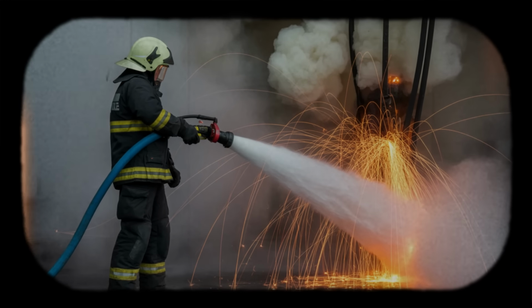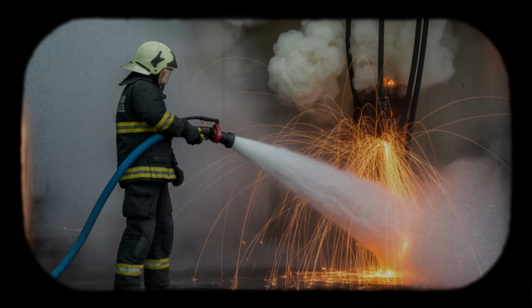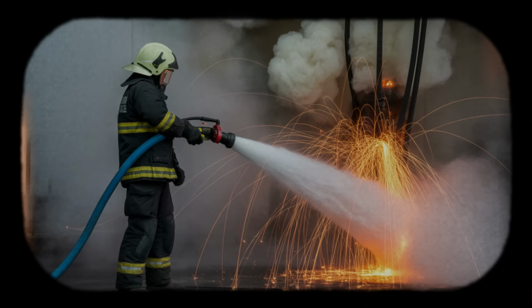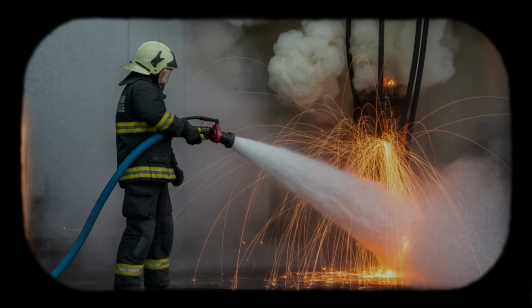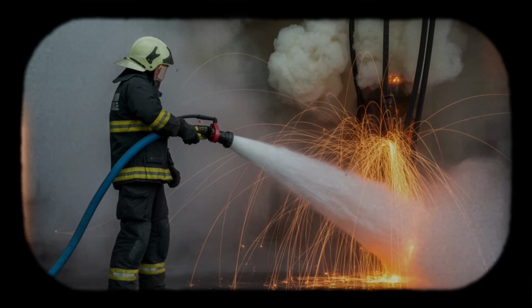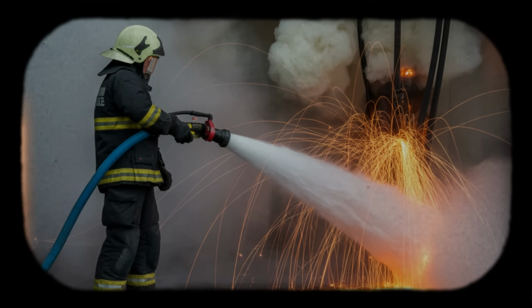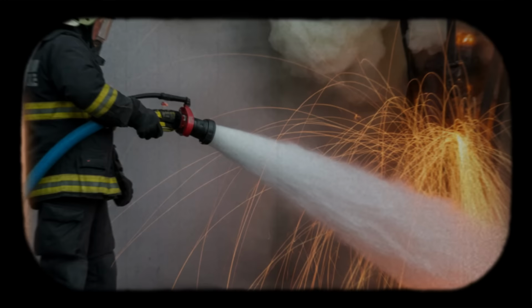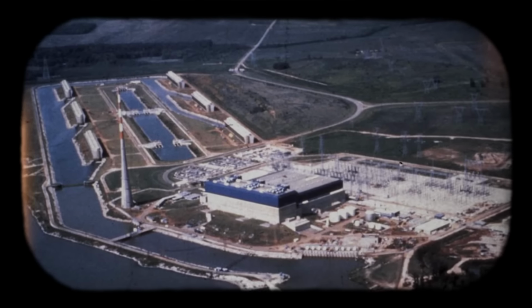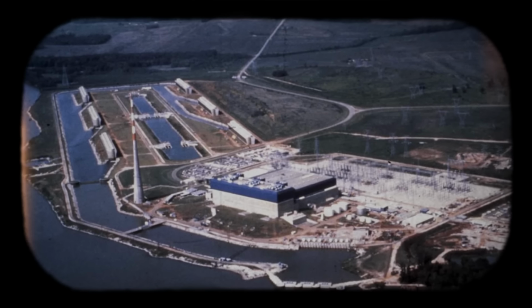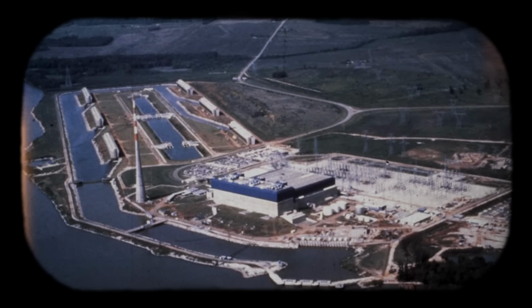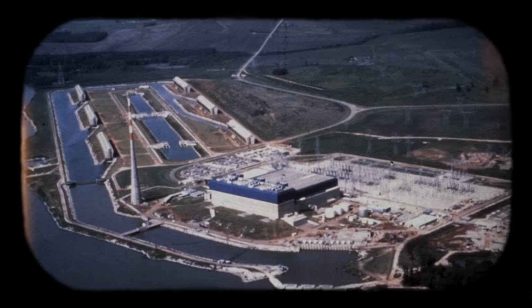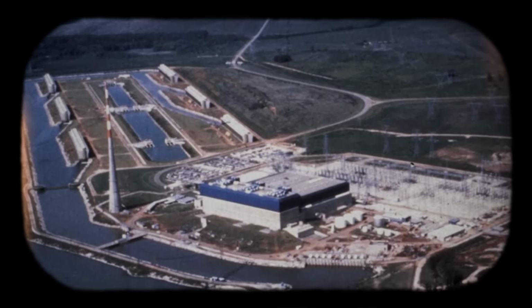Mandatory fire detection and suppression systems are installed in all cable spreading rooms and other areas containing significant concentrations of safety-related circuits. Heat detectors, smoke detectors, and automatic water-based suppression systems provide early warning and rapid response. The goal is to detect ignition within seconds and suppress it within minutes, preventing the kind of spread that occurred on March 22nd. Enhanced operator training addresses fire response procedures.